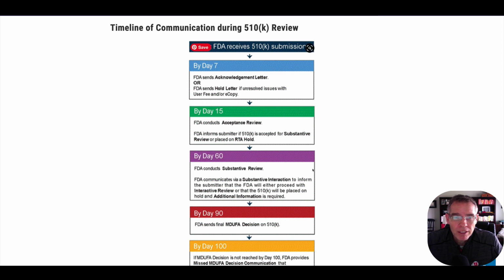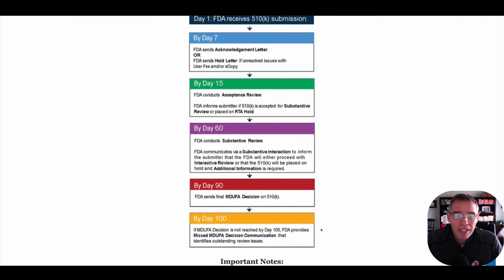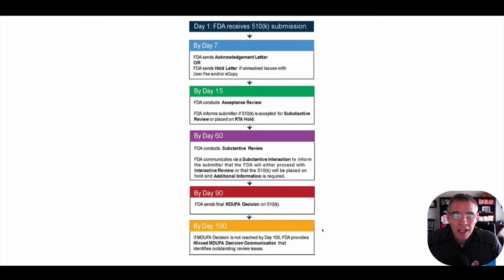By day 60, they plan to complete the substantive review, where the FDA will inform the submitter that the FDA will either proceed with interactive review of that 510K submission, or they place it on hold for additional information. The hold process allows for up to 180 days before the submitter responds. Those days are not counted within this timeline. By day 90, the FDA aims to send a final decision on the 510K. If they can't get that out by day 100, then they will communicate that to the submitter and have a conference where they can identify any outstanding issues.